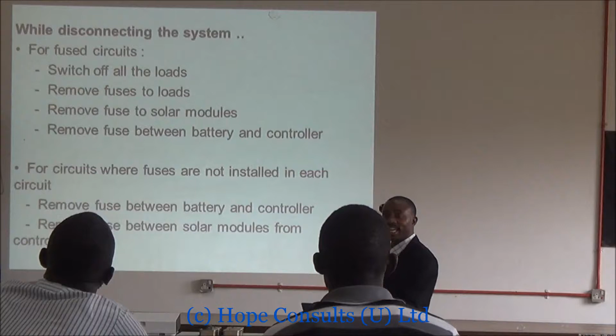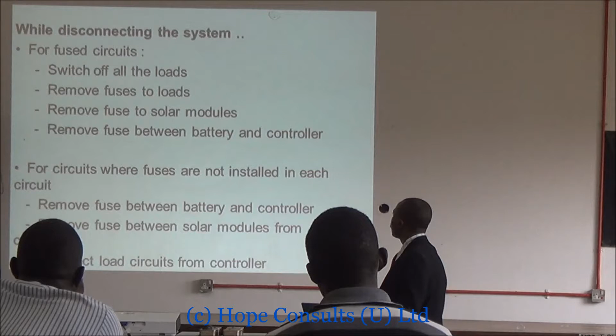While disconnecting the system, remember we are installing, we are checking, we are testing, and we shall commission. For fuse circuits, you first make sure everything is off. You switch off everything, you remove the fuses to the loads, you remove the fuse to the solar modules, and you remove the fuse between the battery and the controller. Where there are no fuses, you just remove the connection between the battery and the controller, and between the solar module and the controller, because the controller has its own fuse system, but you will see that when we go out tomorrow.